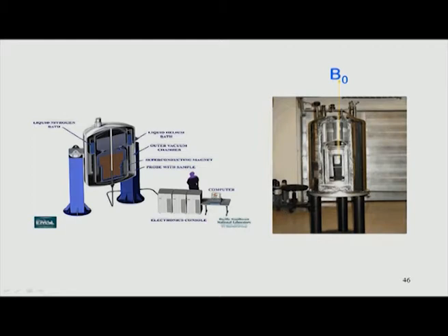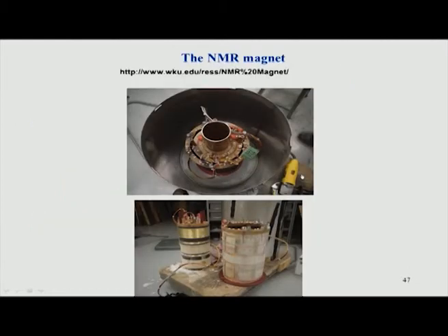You can see this is a cutout of a magnet. This is an old system cut out from a non-functioning machine. You can see the interior of this; it is like an anatomy of a magnet. You can see different layers of the magnet one inside the other, and in the middle there is the bore. This hole runs from the top of the magnet to the bottom, and you can see the coil surrounding this bore. We will look more closely at this coil in the next slide.